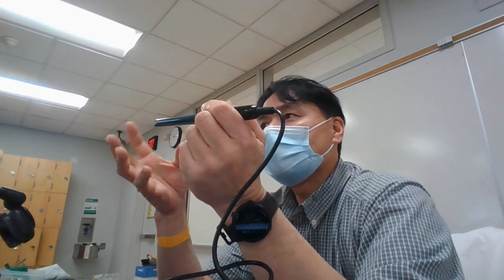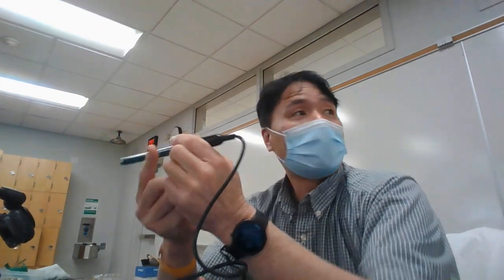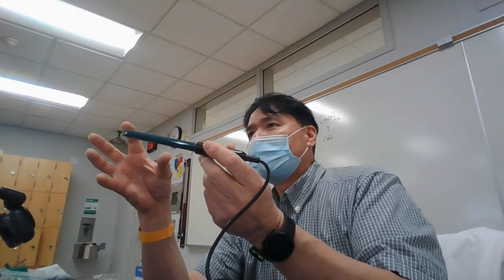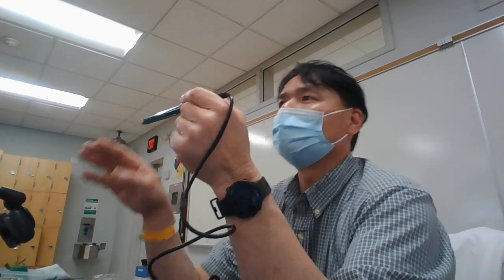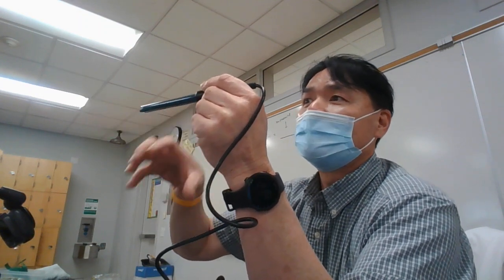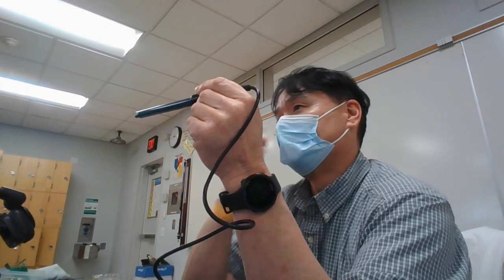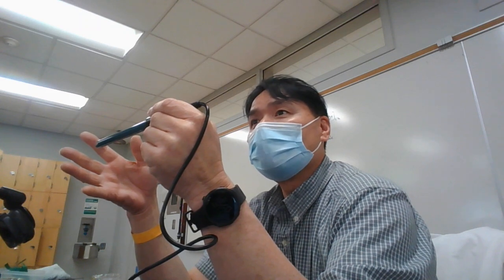You can work individually or you can work together. The probe tip: on the outside surface of the glass bulb is a membrane, a gel membrane. And the gel membrane is very sensitive to hydronium ions. So if we build up a concentration of hydronium ions on the outside, and we compare that to the positive charge on the inside, we could create what's called a voltage. That is, if there's more positive charge buildup on the outside than on the inside, we're going to set up what's called a voltage or an electrochemical potential. That voltage is going to be sensitive to how much hydronium gets stuck on the outside of this.